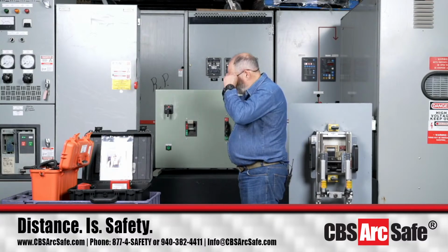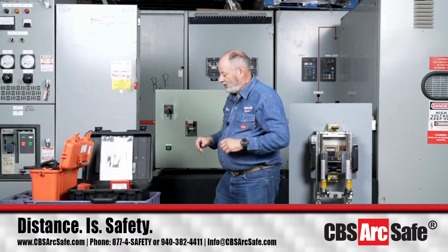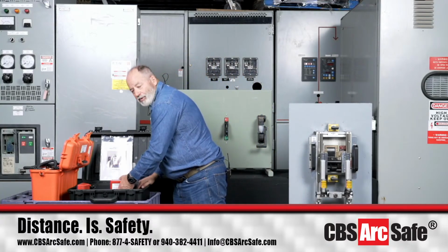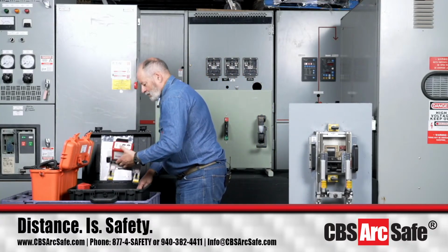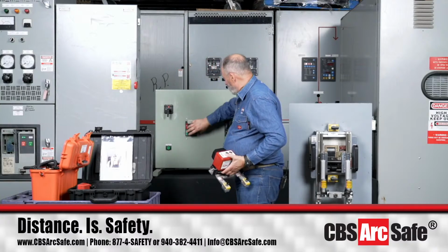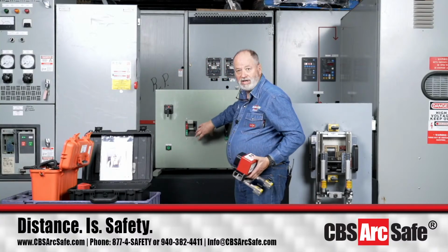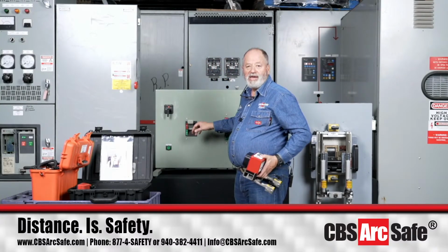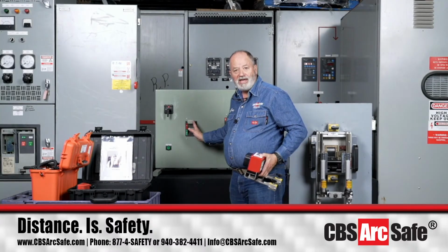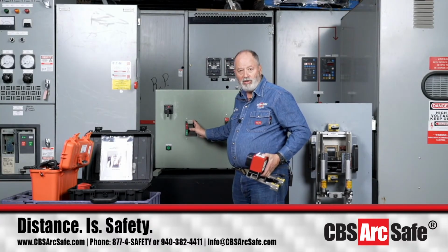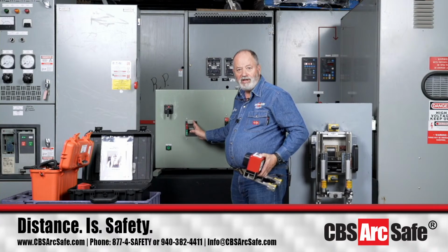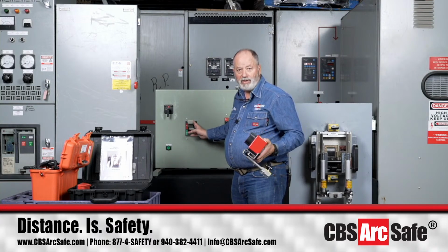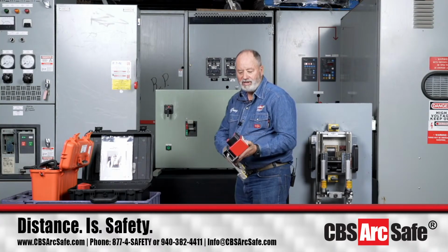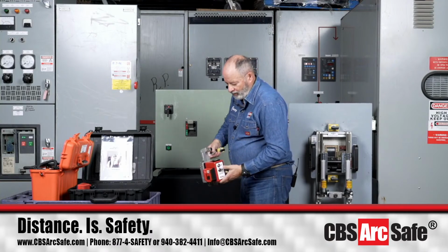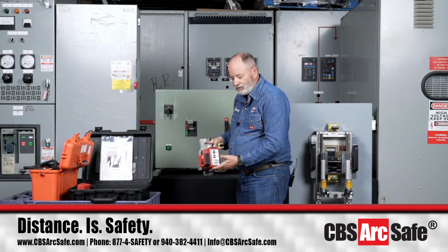This particular device is made for operating even a double bucket setup. So if you've got a handle here and a handle here, it's going to set up just fine. The only thing you may have to watch out for is if you have a lockout tagout on the left handle, you may have to remove it if you cannot properly locate the actuator onto the right one with that in place.